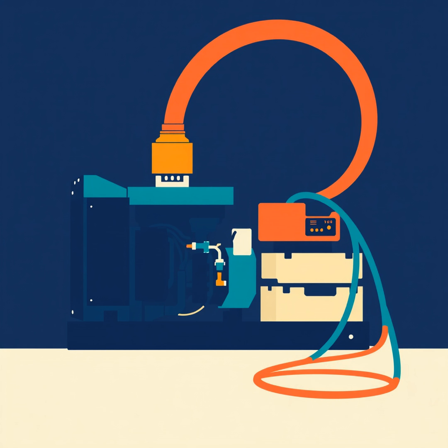No, not at all. We are talking about massive diesel or natural gas engines the size of semi-trucks. In a Tier 4 data center, for example, you do not just have one backup generator, you have what is called N+1 or even 2N redundancy. If the facility needs 10 megawatts to run, you might have 12 generators, each capable of 1 megawatt. That way, 2 can fail or be down for maintenance, and you are still fine. That is N+2. But in a 2N system, you have 2 completely independent power plants. If one entire side of the building explodes, the other side carries the full load.